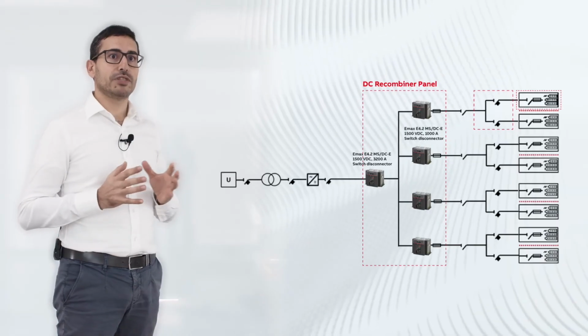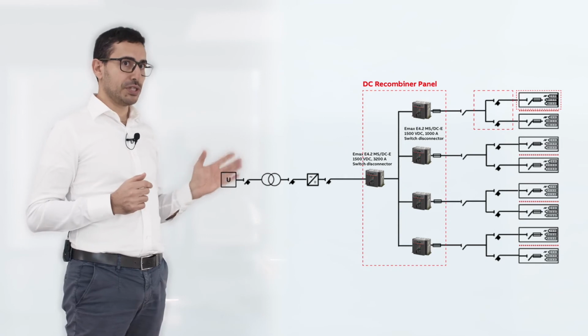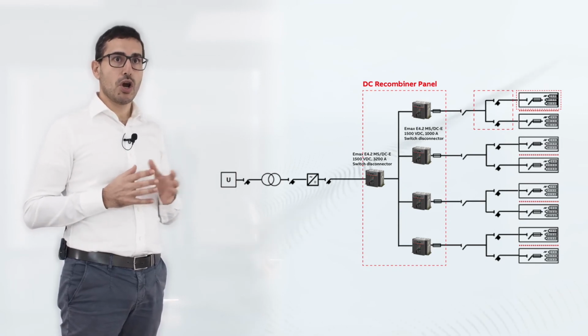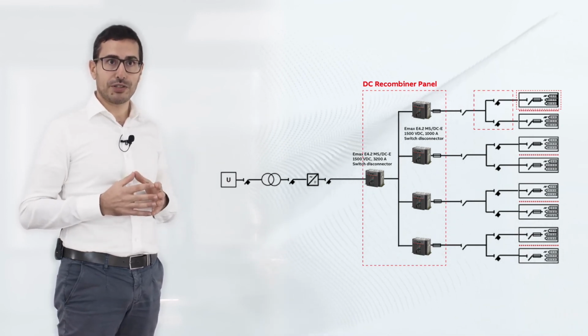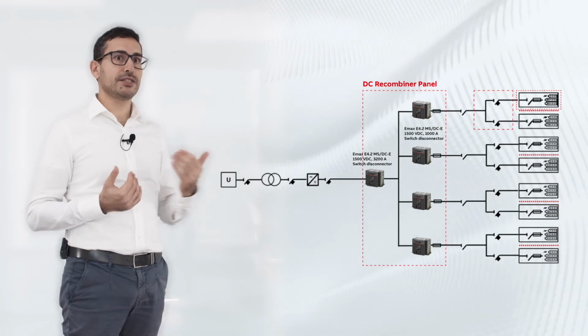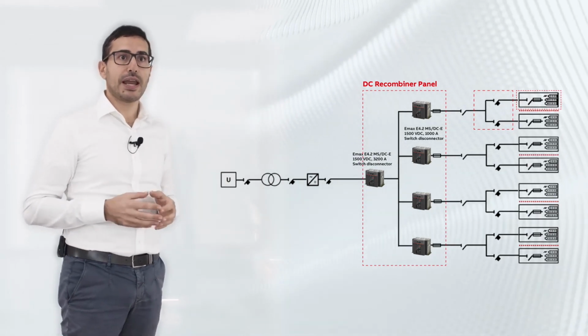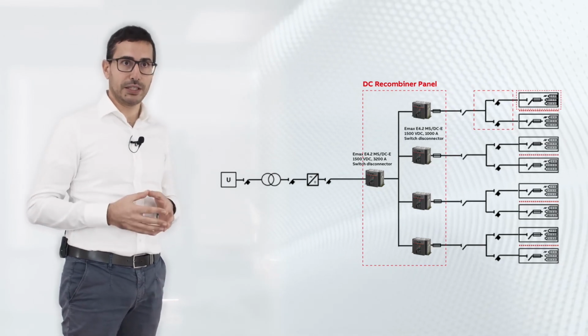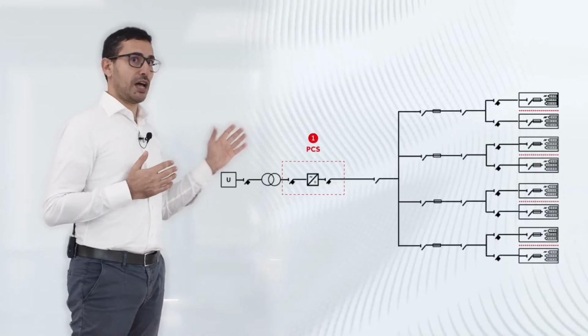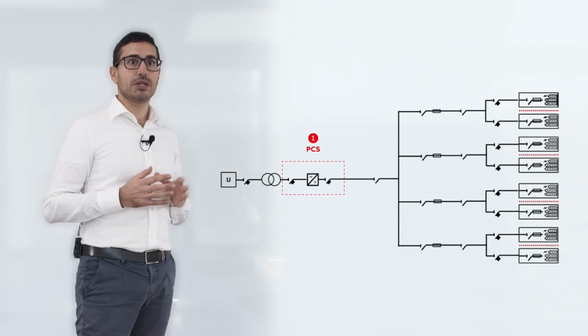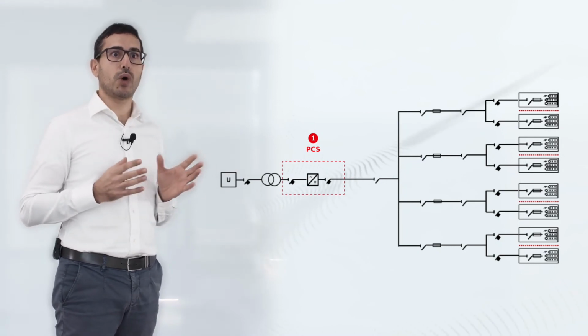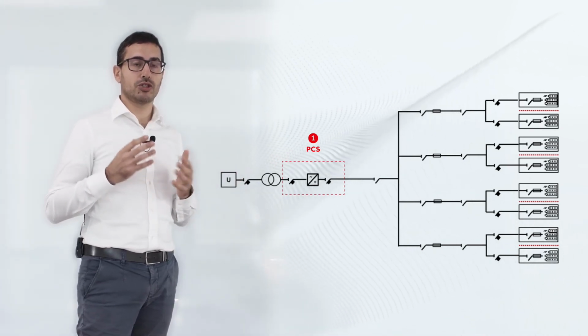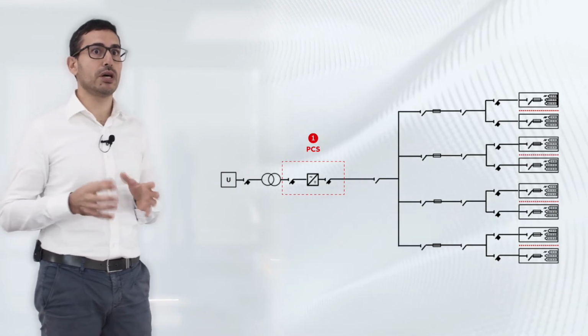On the left side of the circuit, we may see the PCS, the power conversion system, which is a bidirectional inverter which provides charge and discharge of the batteries. Upstream and downstream, so AC side and DC side of the PCS, an appropriate protection and switching device must be provided. It's not just a matter of protection and switching, but also it's about connectivity, since those devices have to be integrated with a BESS control system. On the DC side, we may see an E4.2 switch disconnector, 1500 volt DC, 3200 amps, which provide overcurrent and short circuit protection in combination with the fuses installed inside the PCS.